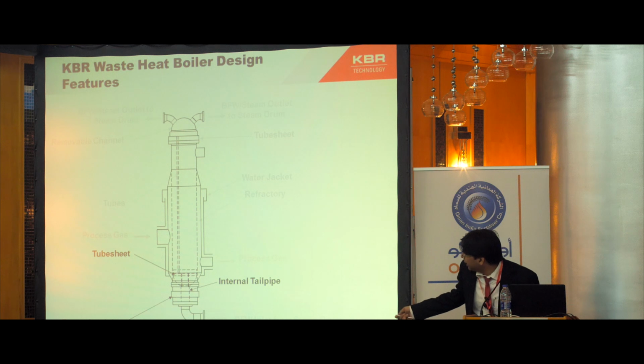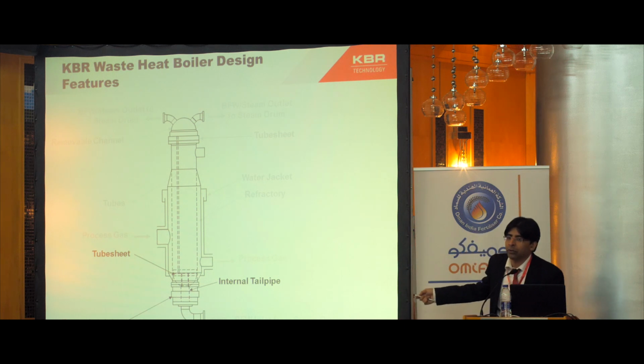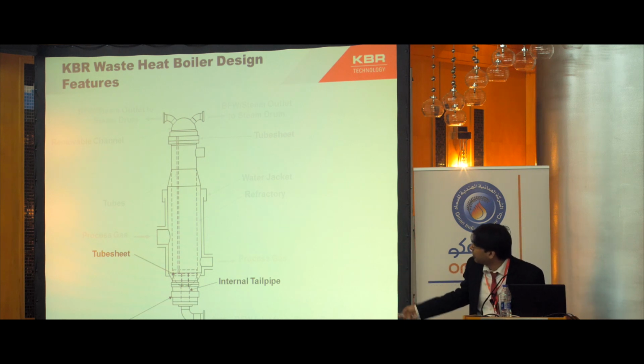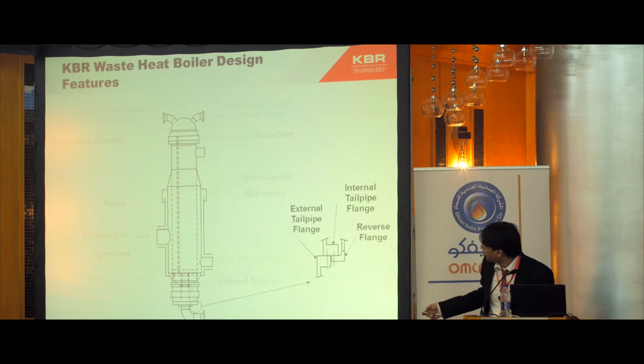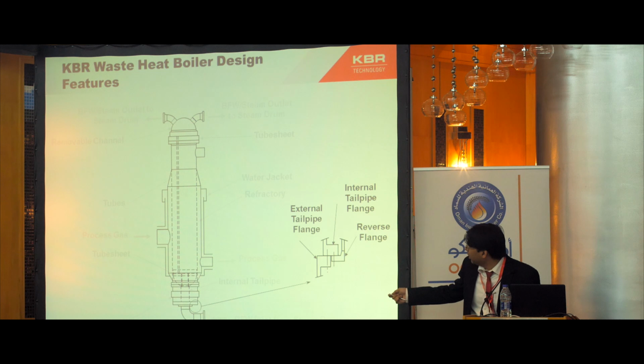At the bottom of the boiler feed water side there is an expansion joint, so as to take care of the thermal stresses as well as the weight of the bundle. So this is the internal tailpipe for the boiler feed water coming into this floating head section.